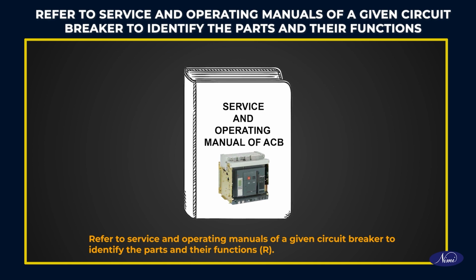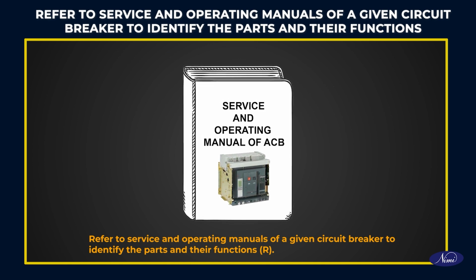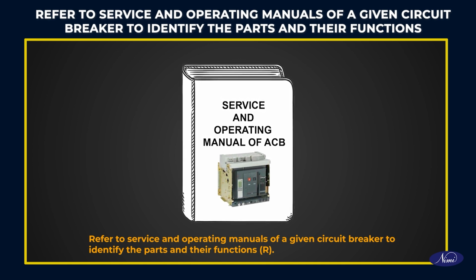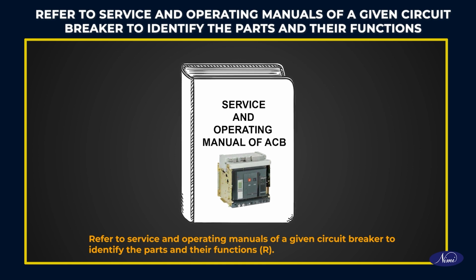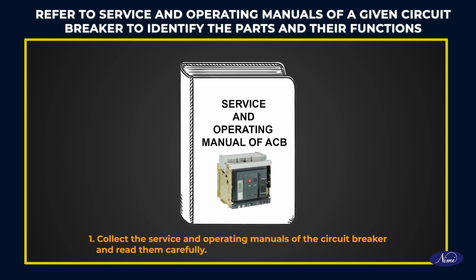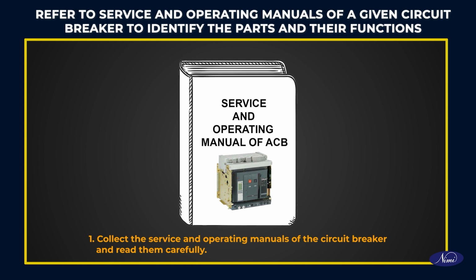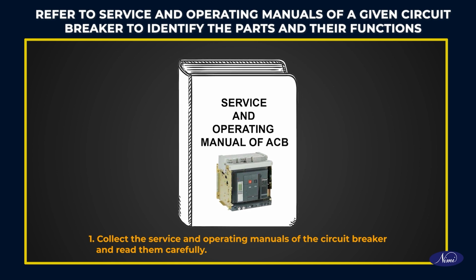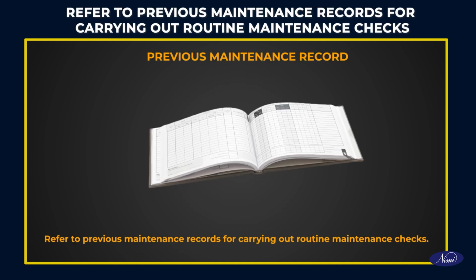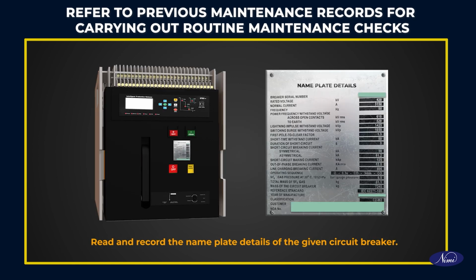Refer to service and operating manuals of a given circuit breaker to identify the parts and their functions. Collect the service and operating manuals of the circuit breaker and read them carefully. Refer to previous maintenance records for carrying out routine maintenance checks. Collect and read the maintenance record sheet of the circuit breaker. Read and record the nameplate details of the given circuit breaker.